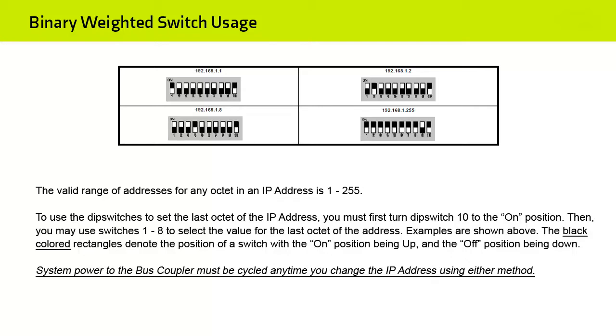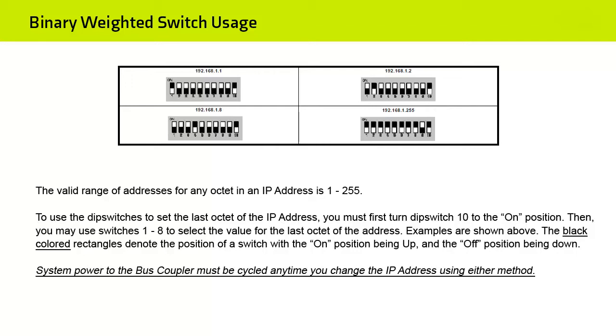To use the DIP switches to set the last octet of the IP address, you must first turn DIP switch 10 to the ON position. Then, you may use switches 1 through 8 to select the value for the last octet of the address. Examples are shown above. The black colored rectangles denote the position of a switch, with the ON position being UP and the OFF position being down. System power to the Bus Coupler must be cycled any time you change the IP address using either method.